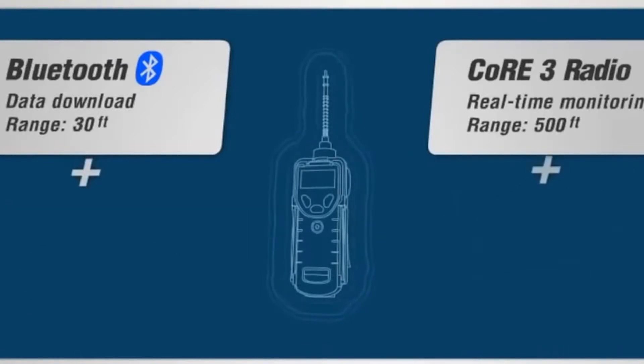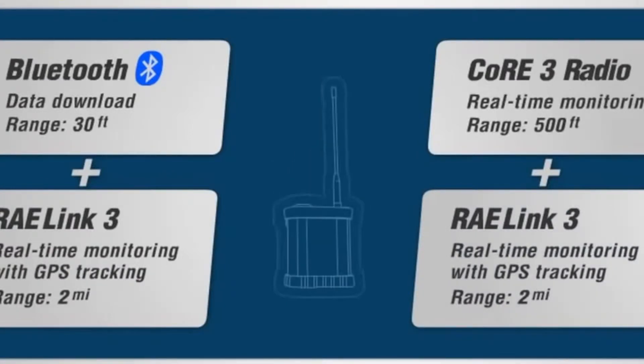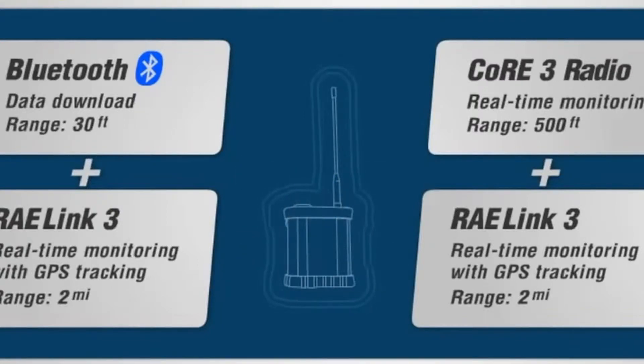The addition of a RAELink 3 modem enables wireless transmission of gas concentrations and alarms to remote computers in safety rooms or command centers up to 2 miles away. The RAELink 3 also has a built-in GPS antenna, which reports your position to within 25 feet.